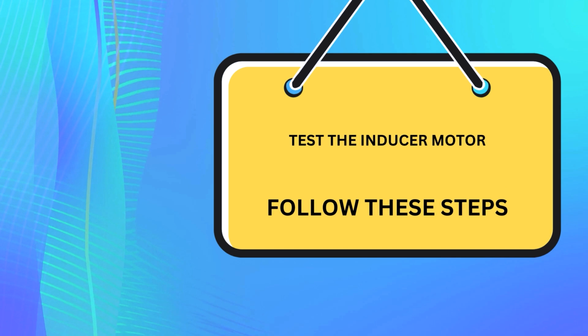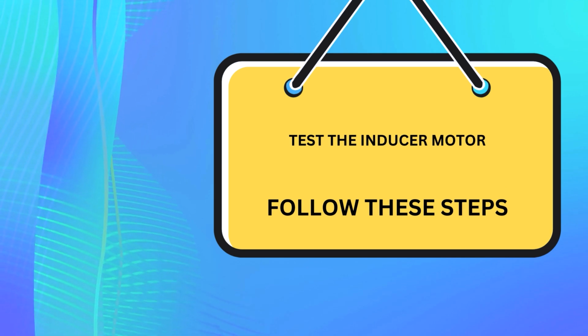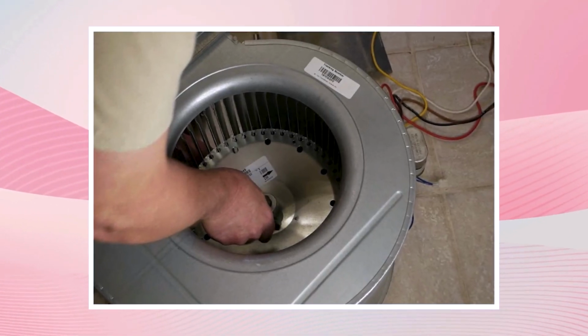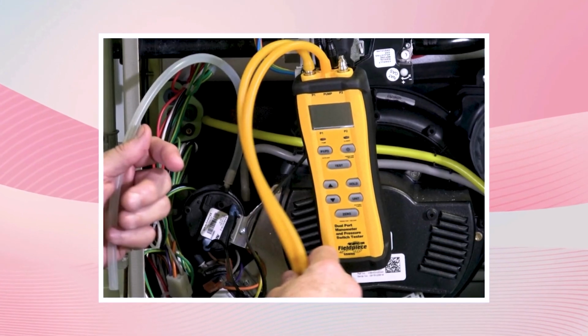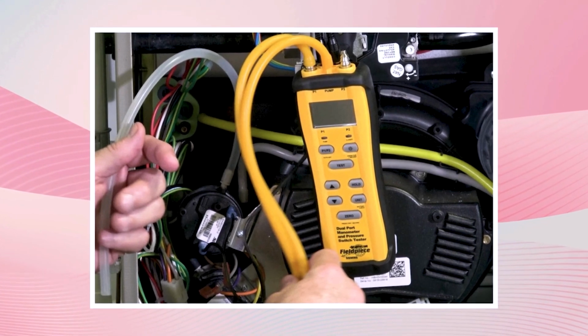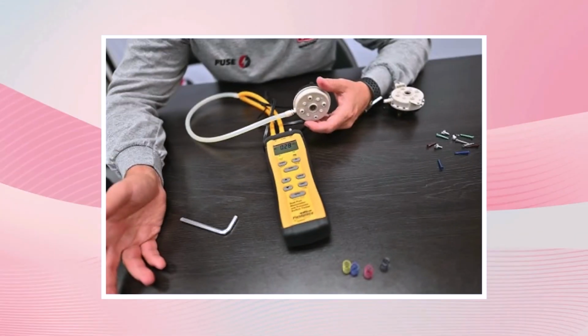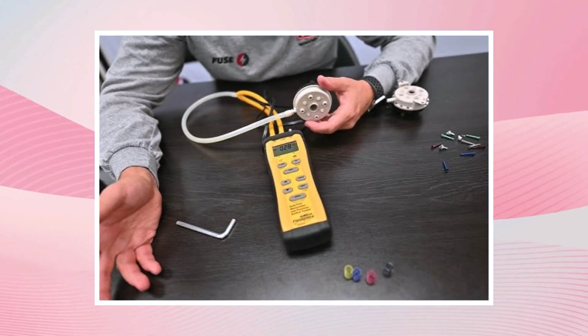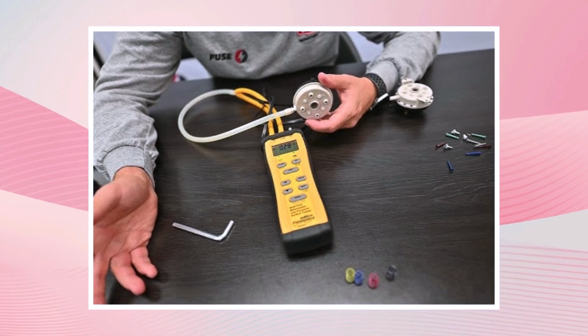Test the inducer motor. Follow these steps. Listen for any abnormal sound. Use a manometer to measure the pressure produced by the inducer motor. If the level as displayed is not the right level, consider repairing it or replacing it.